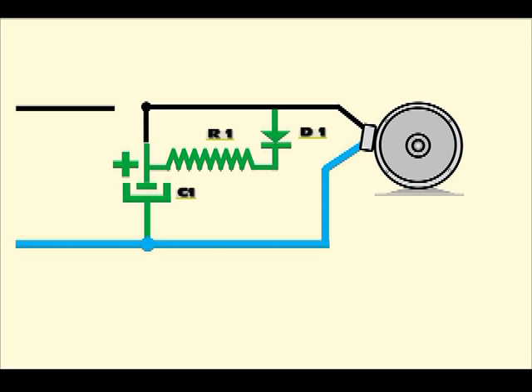When the motor is turned off by means of switch S1, the capacitor is discharged through the motor winding, and the stator acts as a strong electromagnet, inducing an intense current in the short circuited bars of the rotor. This current in turn produces a strong magnetic field in the rotor which opposes its motion, bringing the motor quickly to stop.